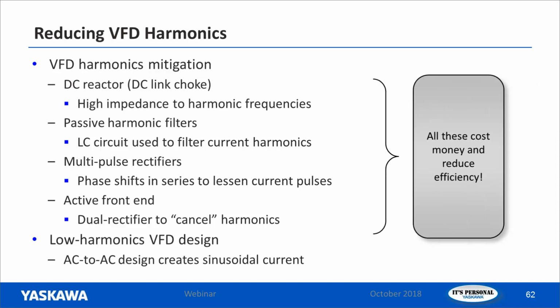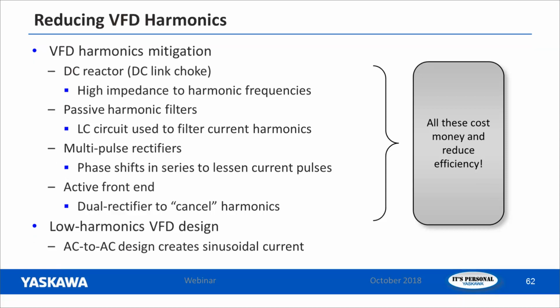One thing all of these mitigation options have in common is they do cost a little bit more money. If you think about it, your cheapest solution on a drive is going to be a straight 6-pulse drive that doesn't have any harmonic mitigation. So if you add harmonic mitigation, you're going to be adding some cost to the system. And it could reduce efficiency as well.